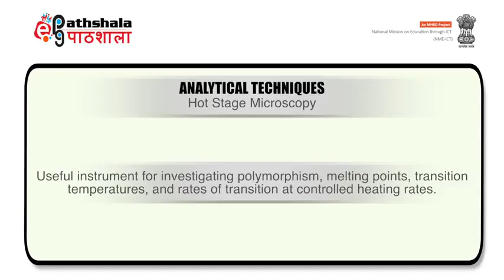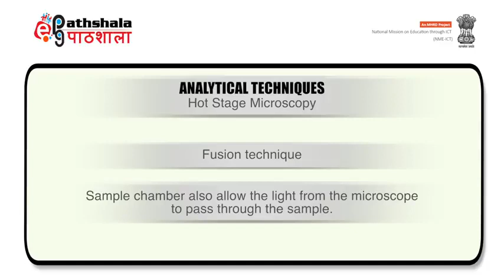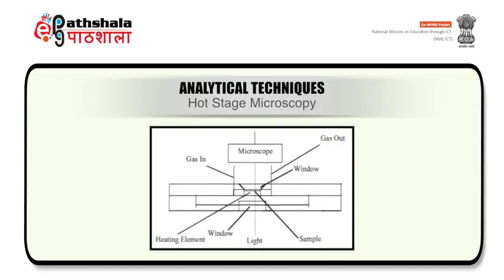The polarizing microscope fitted with the hot stage is a useful instrument for investigating polymorphism, melting points, transition temperatures and rate of transition at controlled heating rates. Hot stage microscopy is a fusion technique where the sample can be heated at different rates in the sample chamber and the atmosphere can be controlled. The sample chamber also allows the light from the microscope to pass through the sample. Direct observations by hot stage microscopy can reveal subtle changes not readily detected by other instrumental techniques.